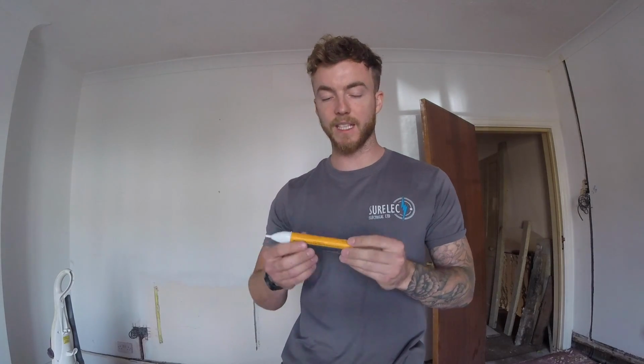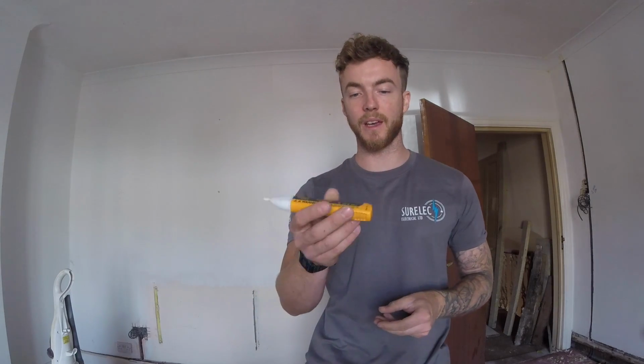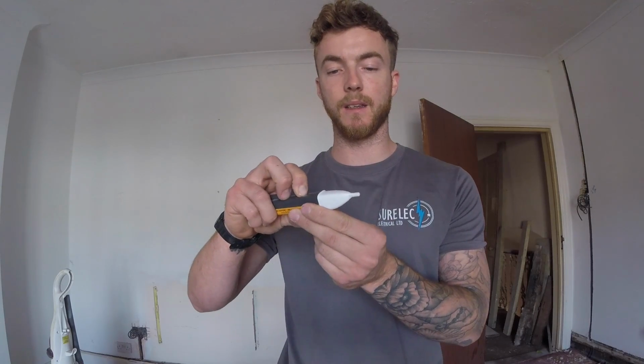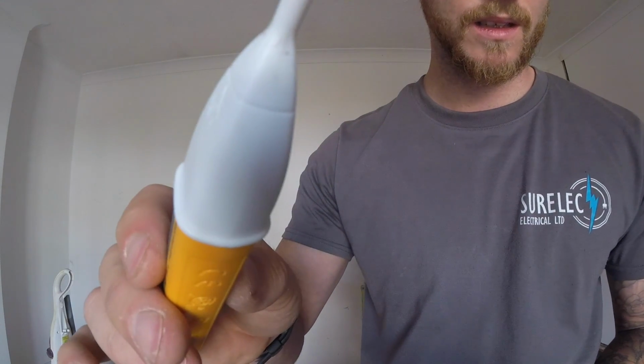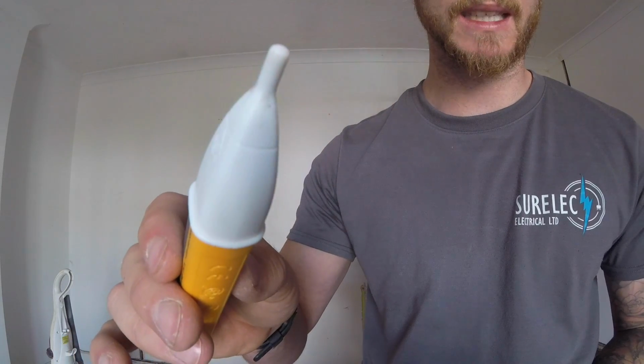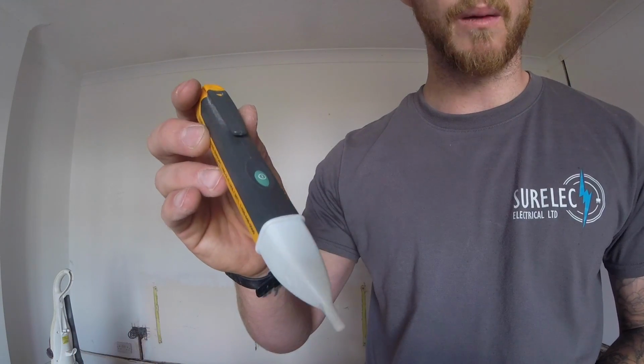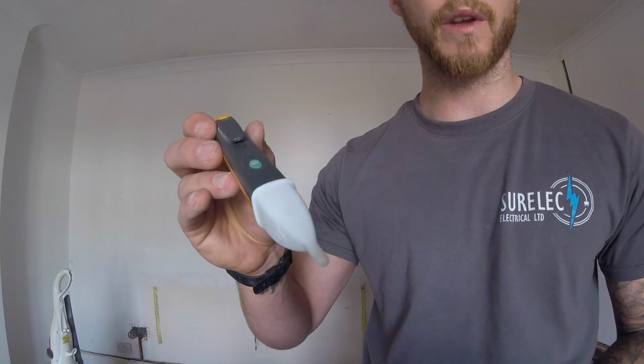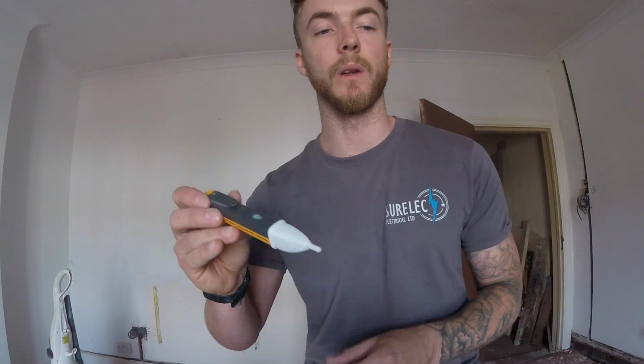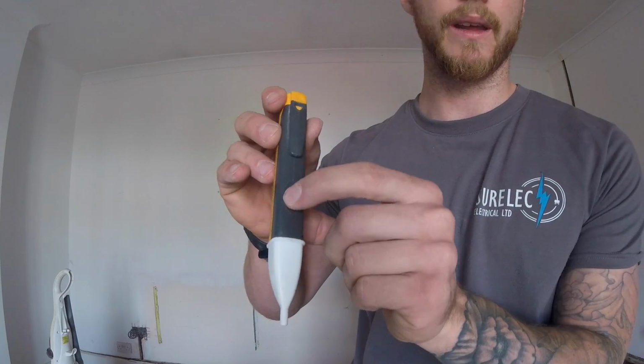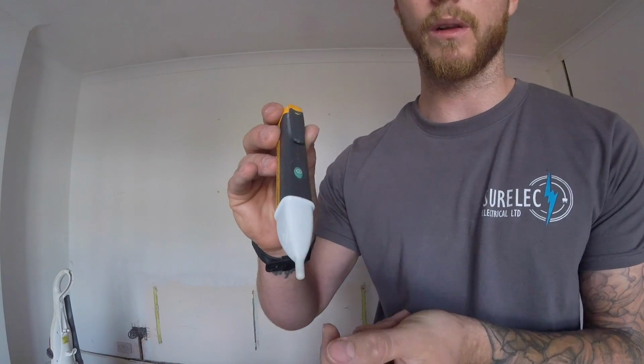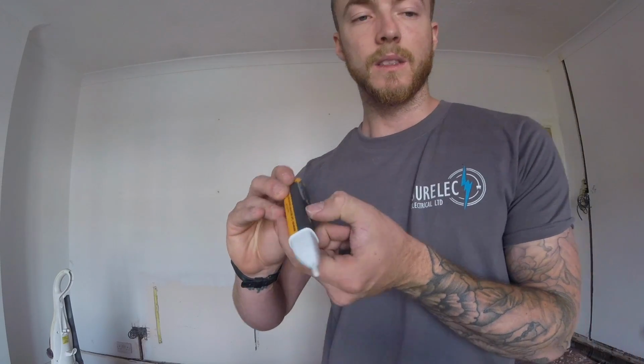Right, so my next bit of test equipment in this video is the Fluke, what's the model number of this? Volt Alert 1AC-E. So this is a non-contact voltage indicator. It also gives a nice little flashy red light while it's testing. Just show you that. So that flashes away just to let you know it's ready to test. And then when you do touch that on a live cable on the sheath and anything, that'll glow red and also give an audible tone. So that literally just turns on by that on and off button, and hold it down to turn off, and that'll give you a notifiable little beep. So yeah, these are quite controversial.